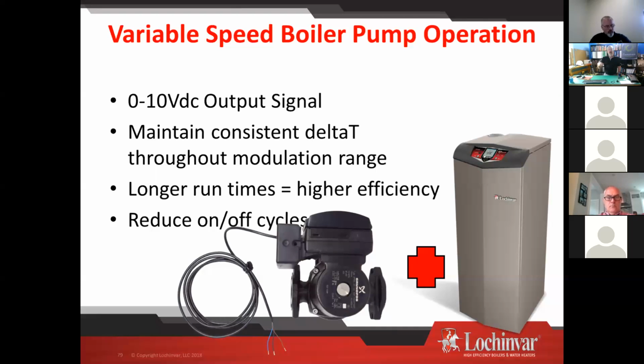The reason we do that, and you're going to tell the boiler it's a variable speed pump, is because, in a sense, there's a drive in there. There's a little VFD drive, if you will. We keep that pump powered all the time. The boiler turns it off using the 0 to 10 volt signal, and turns it back on the same way. So it's kind of a neat little feature that's right there in the boiler now.